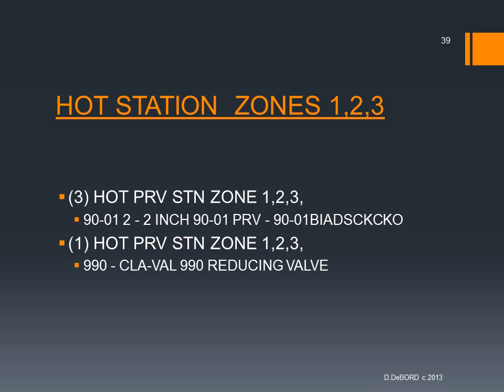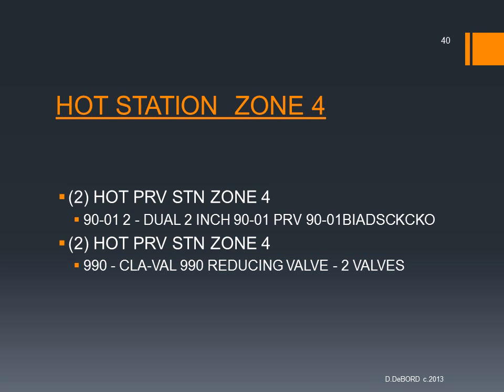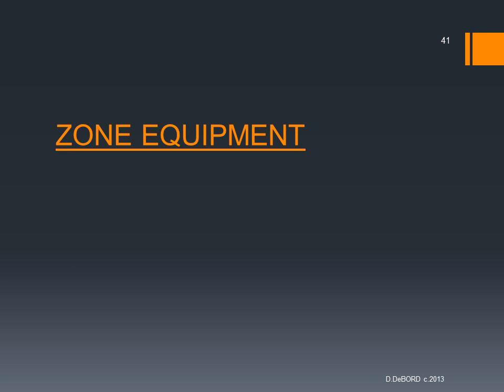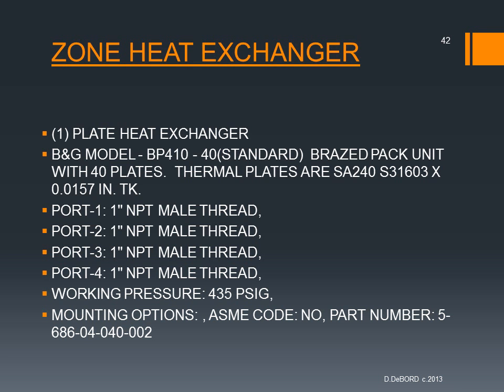You need a PRV schedule. These are the hot water PRV stations. It's not in a schedule format, but it's easier to see here in this format, I believe. Here's the hot station zone 4. And then we look at the zone equipment. By that we mean those zone recirc systems, secondary heat loops.